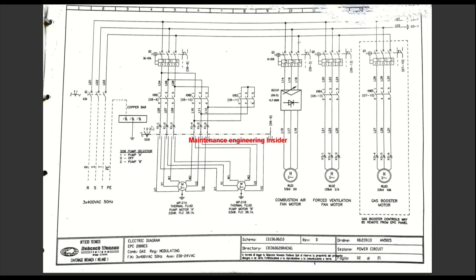These two motors run in star-delta. When you switch on to one pump and start it, it goes star-delta and that motor runs. If you switch to the other pump, it also goes star-delta and that one runs. Since there's no power coming here, we need to find the coils of these contactors. We can see they are all on sheet number eight: section eight, section ten, and sector line eleven respectively.